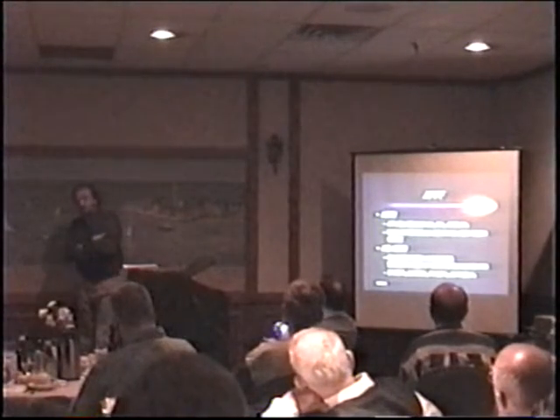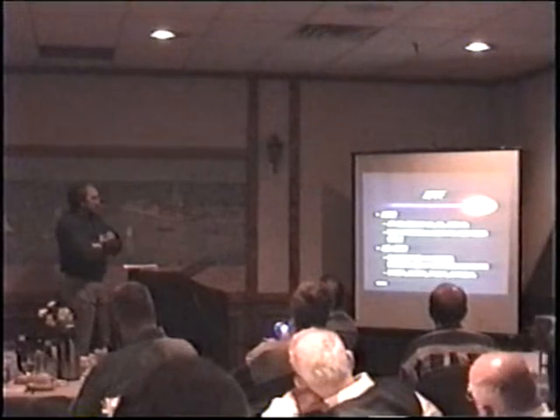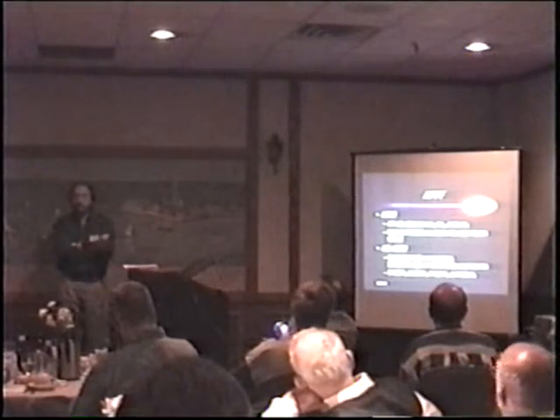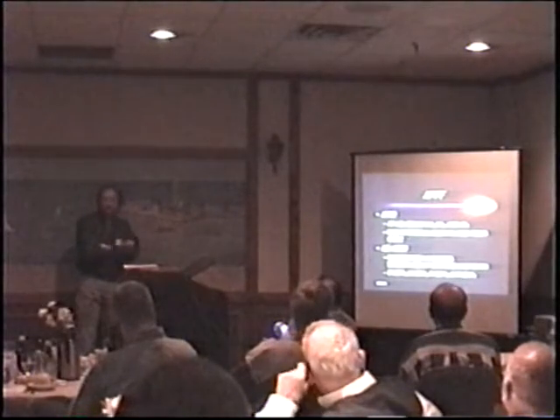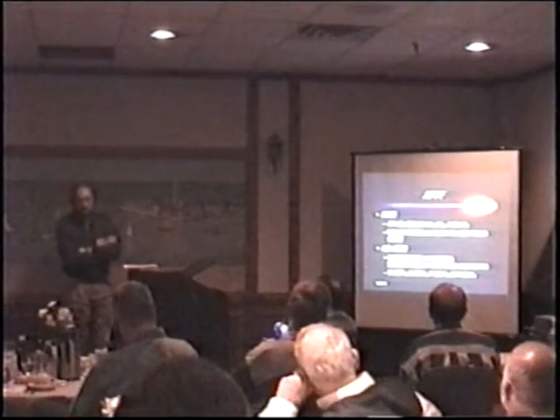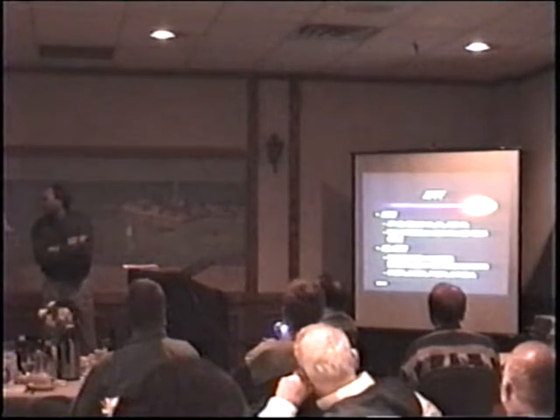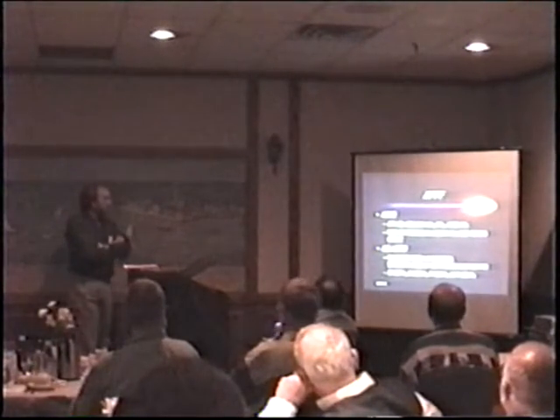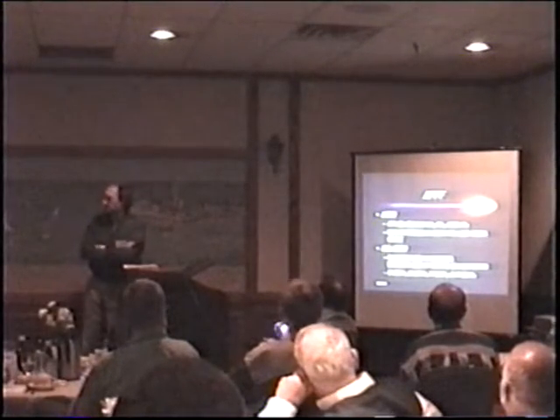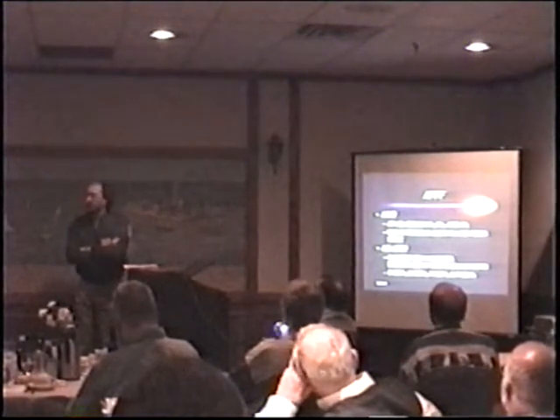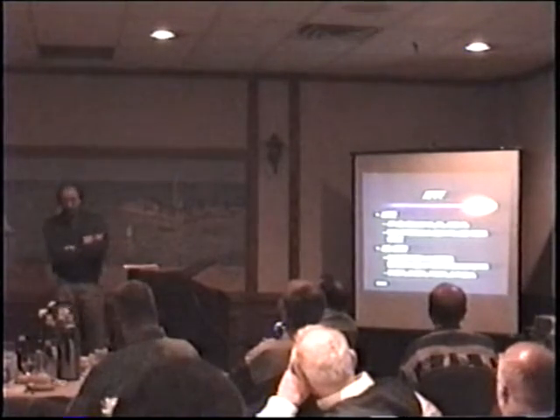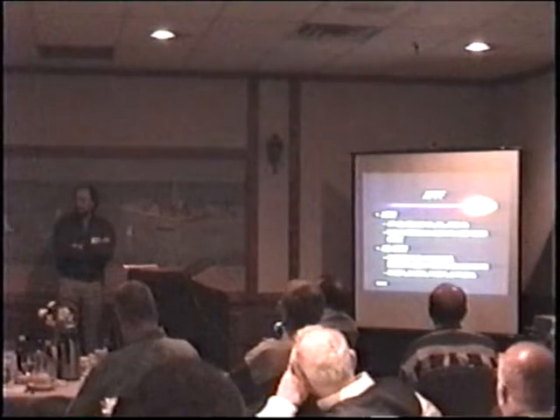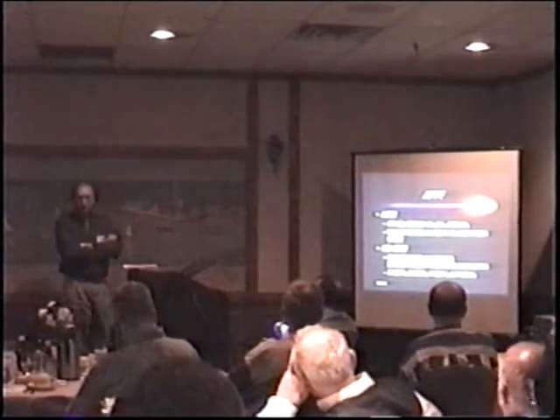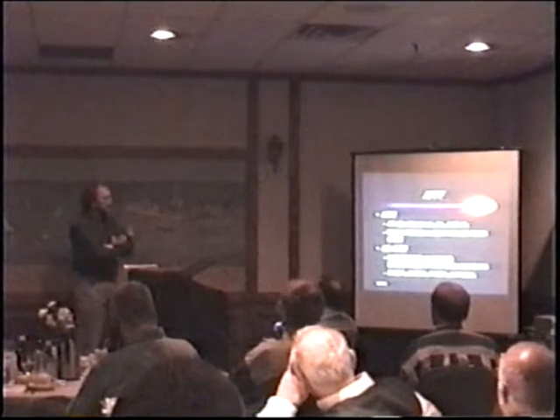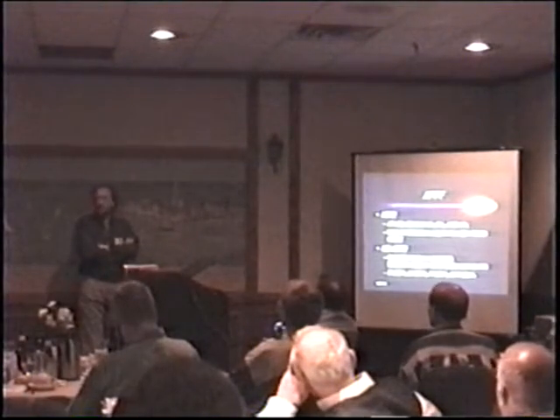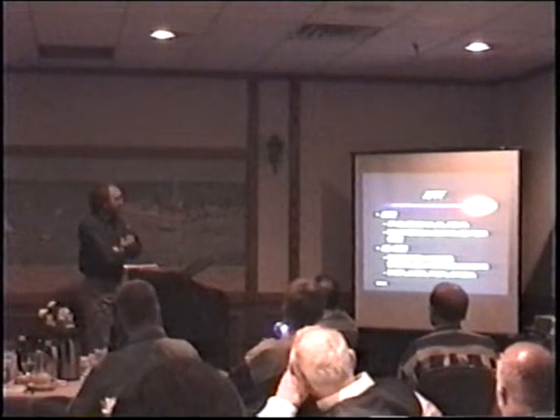AFFF basically comes in two varieties. The base AFFF, which is available at 1, 3, and 6%. Very seldom do you see a 6% AFFF used anymore. It's just not cost effective to have a 1,000-gallon tank when you can have a 500-gallon tank. 1% has been around for years and years, just never really caught on. I think there's still a little bit of a mental block connected with 1% proportioning margin of error. What if the orifice plate, which is fairly tiny, plugs up? You see it mostly in large volume applications, like airplane hangars, where you'll see 1% most often.